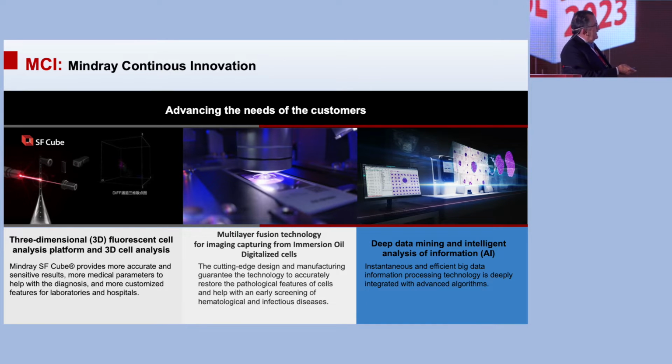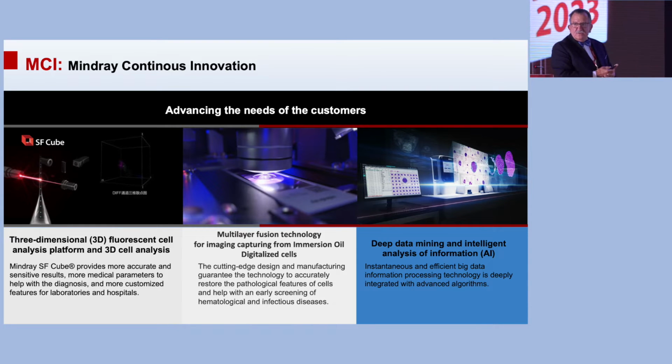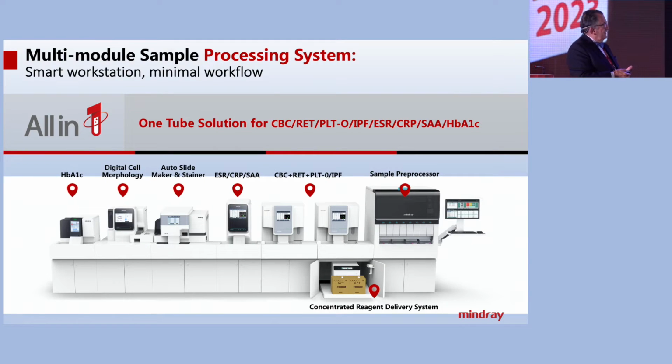You can see here in this center slide it is doing multi-layer focusing with immersion oil. That is the only technology that uses immersion oil with a 100x objective to do a perfect visualization of the cells, able to do diagnosis. Before that, many of the users had to look at the smear under the microscope to see if there were blasts, and of which type. You can do it for screening, but for the diagnosis they went to the microscope. Here it is not necessary anymore because you have a 100x immersion oil objective.